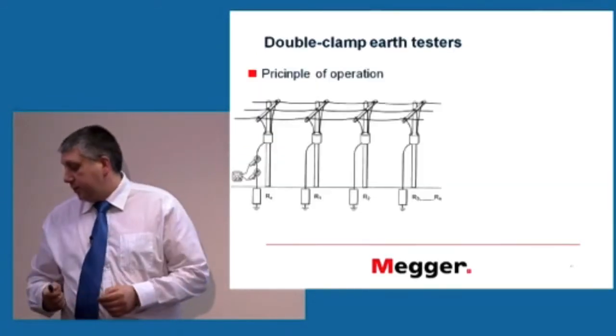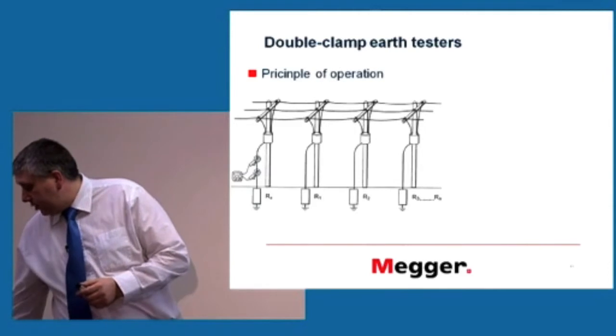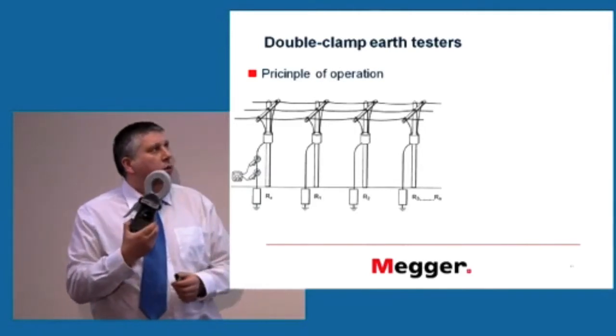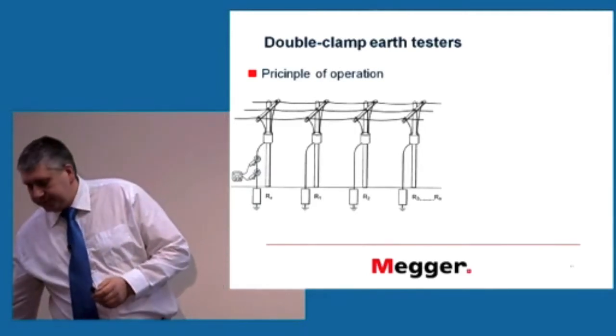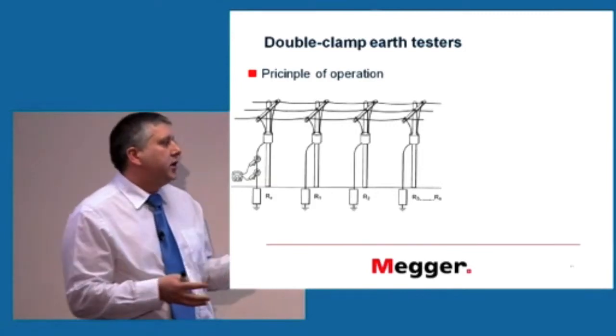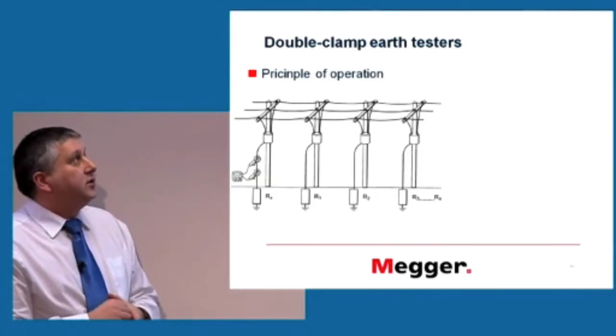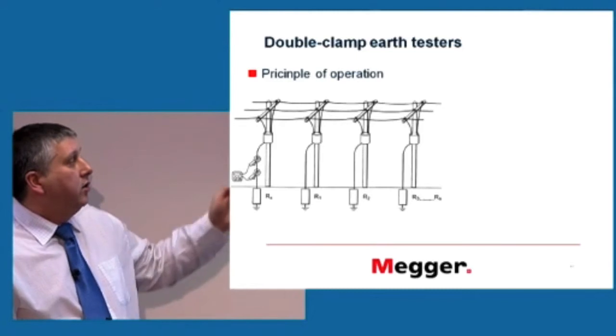So this was just a current transformer. Now I will say something about double clamps. What is that double clamp earth tester? Earth testers are designed, as the name indicates, for testing earth connections.